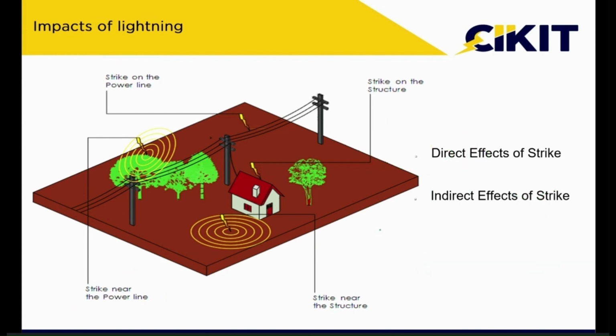In many industries, failures of electronic equipment have happened because of a lightning strike near the power line. So if we want to provide complete protection, we need to ensure that we are covering all four sources through which lightning will cause damage. If we cover all four sources, we can ensure complete protection against lightning.